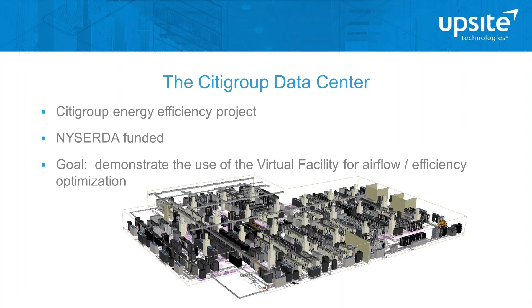When we ran the calculations, similar to what we showed earlier, the first goal was energy efficiency, going after the lowest hanging fruit first and then increasingly moving to more difficult parts. So non-invasive, no-cost or low-cost solutions with stock available on site came first: changing floor grills, blocking gaps in the floor, cabinet blanking, the sort of thing Upsite focuses on. By running the simulation, we could point exactly where to do this for the best effect on the room. So we did everything you see on the right-hand side for item 1.